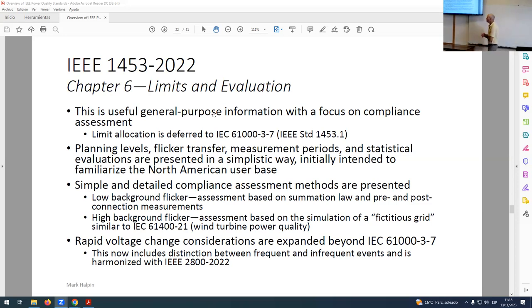Okay. The main takeaway here, or the main contribution for chapter six, the biggest one is this third sub-bullet. Voltage fluctuations, as you're well aware, are the result of all network users operating together. A major issue when it comes to anything associated with flicker management and flicker limits is to determine who's doing what, because if you go and measure a voltage, you're measuring the result of everybody. If you want to give a customer a flicker limit, there are procedures in IEC 61000-3-7 to do that. So you give a customer a flicker limit, and then you go and you measure flicker. But the flicker that you measure is the combined effect of everybody.